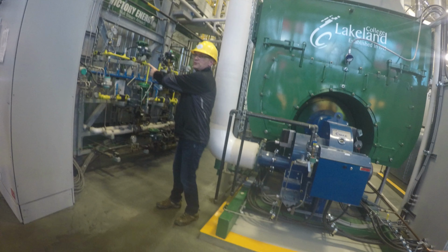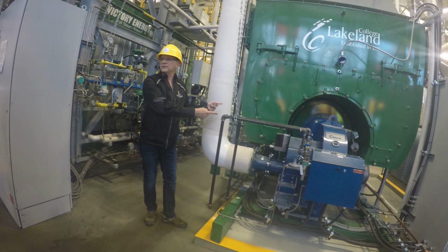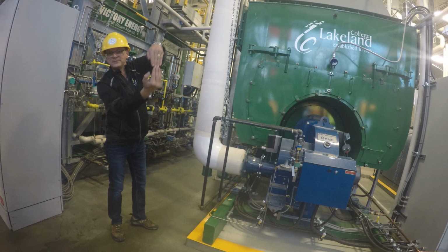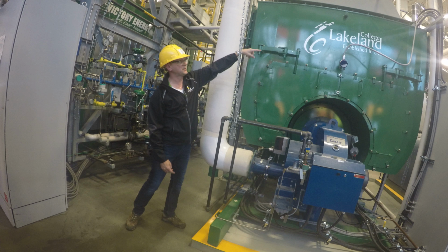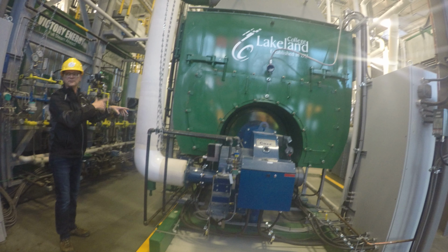This is our fire tube boiler. Now a water tube, like I said over here, your tubes are full of water, so we call it a water tube. Fire tube, your tubes are full of fire. So a typical fire tube is like a drum sitting on its side. We're going to fill this thing up with water up to about that word established, and then we're going to run a whole bunch of tubes from one end of this boiler to another.